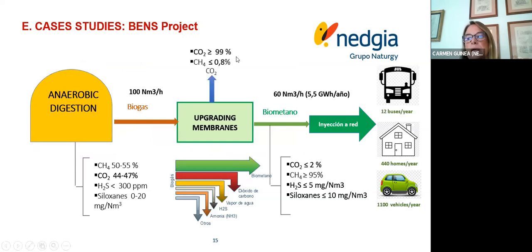This is the view of the plant installing in the biogas. The wastewater treatment plant collects the sludge into 2 anaerobic digesters. The biogas flow is, as I told you before, 100 cubic meters per hour of biogas, and the biomethane 60 cubic meters per hour. The biomethane has over 95% methane. With the energy that this plant can produce, you can fill 12 buses, or supply 440 homes in Spain consuming heating, and 1,100 vehicles per year.